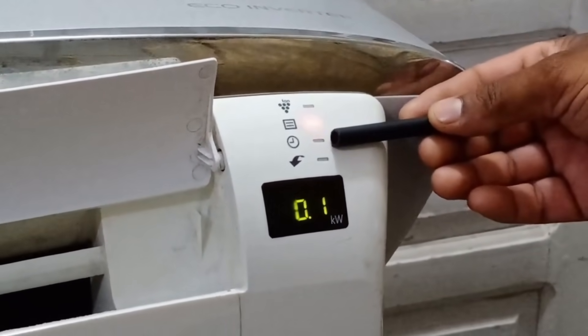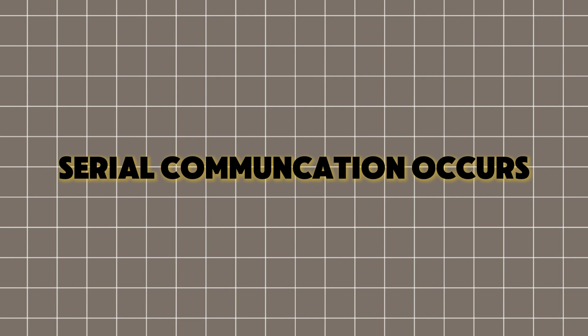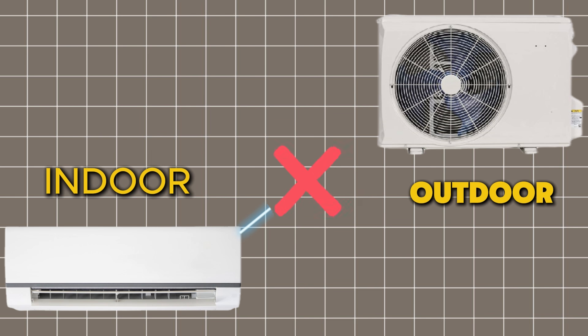This indicates that the issue is a serial communication error. A serial communication error occurs when there is no proper connection or communication between the indoor and outdoor units.